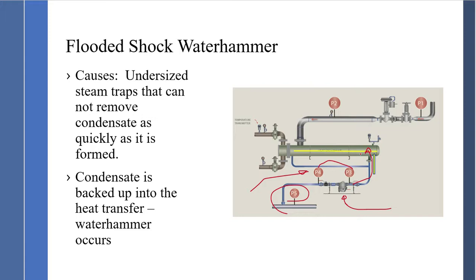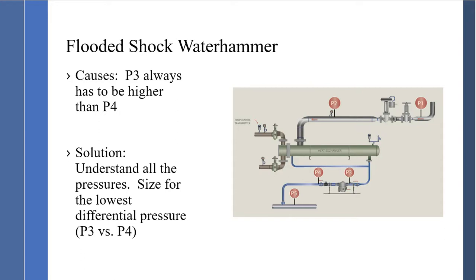Flooded conditions cause tube failure, tube sheet failure, baffle failure, support failure inside the heat transfer plate frames, gasket failure, and gasket material failure — creating many issues. When sizing steam traps, take the time to understand the differential pressures P3 and P4. Always have a qualified vendor support you on the sizing application and know the dynamics of your condensate return system. This resolves many issues associated with flooded conditions.